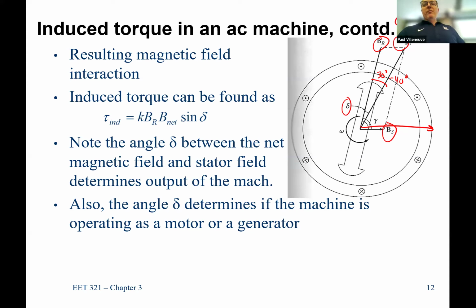If you swap those two, that's a motor. The way you increase or decrease torque is you temporarily slow things down. So if something is spinning at 3,600 RPM and I'm driving a motor, if I put more load on it, what happens for a very brief instant? It slows down a little until that torque angle is large enough to have enough magnetic pull to pull it along. In real time, motors and generators do slow down briefly to increase or decrease that torque angle, but then they get back in sync.